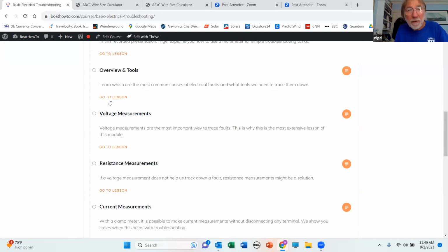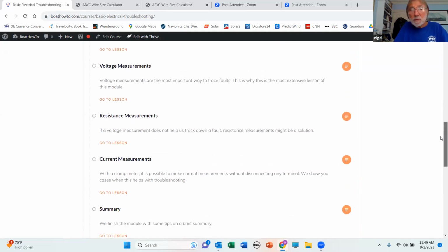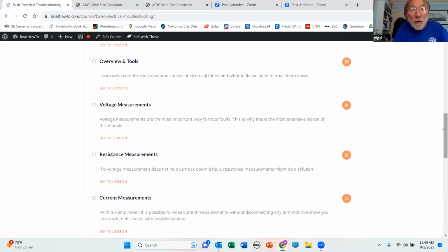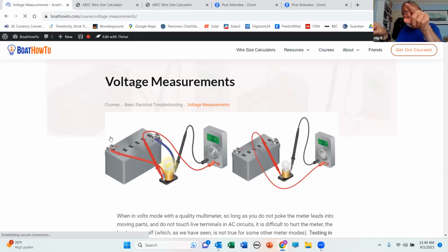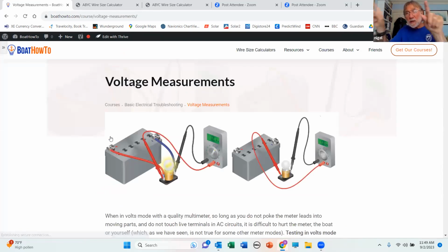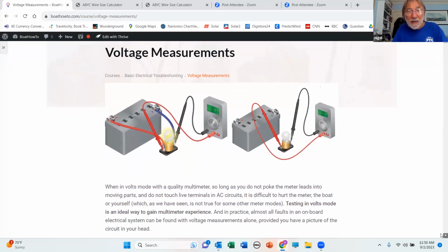And now we're going to stick in the volts mode, because that way it's almost impossible to hurt yourself, the boat, or the meter, as long as you don't poke the probes into moving parts and you don't touch any live AC terminals. So obviously the first thing we do before we go poking around in the boat's wiring is we shut down all the AC circuits, we disconnect the shore power cord, we turn off any generator, we make sure the inverter is turned off so that we don't accidentally energize that.